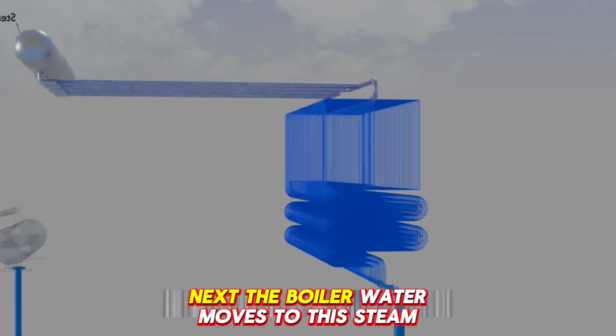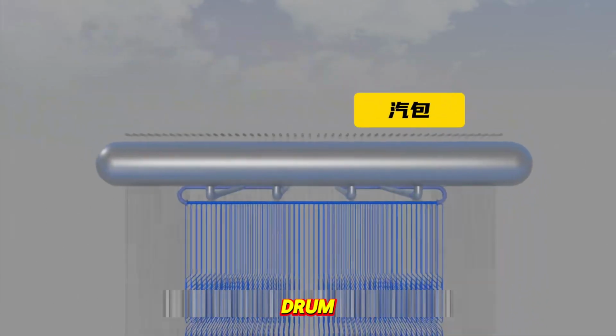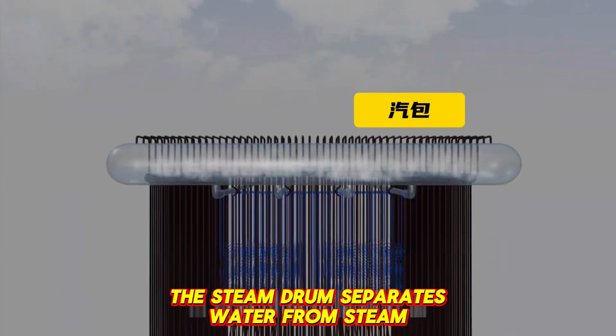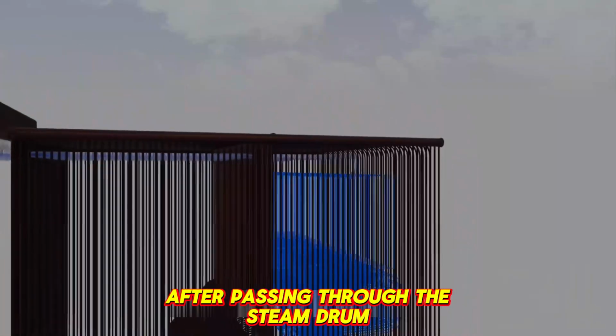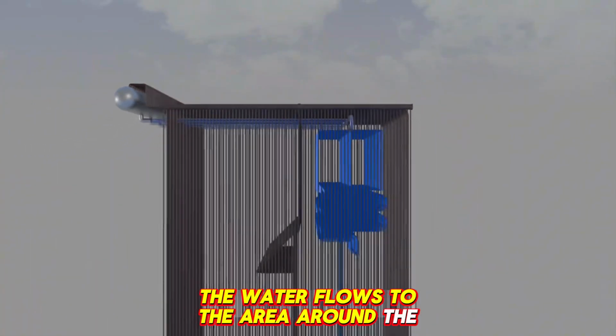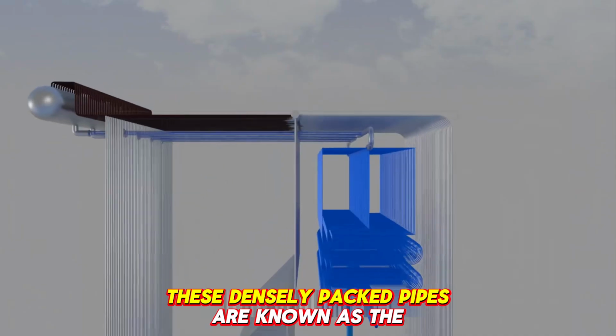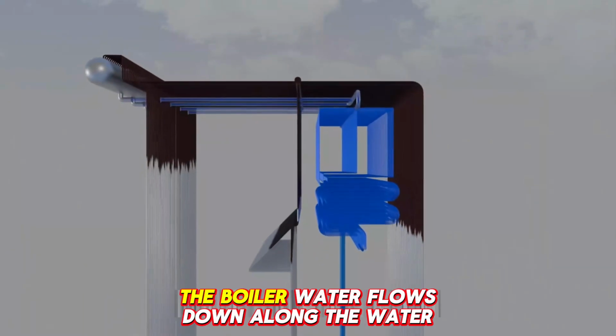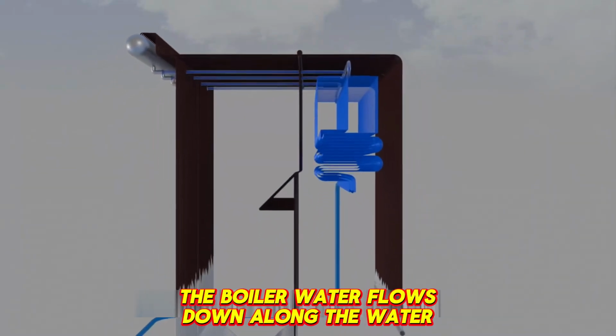Next, the boiler water moves to this steam drum. The steam drum separates water from steam. After passing through the steam drum, the water flows to the area around the boiler. These densely packed pipes are known as the water wall. The boiler water flows down along the water wall.